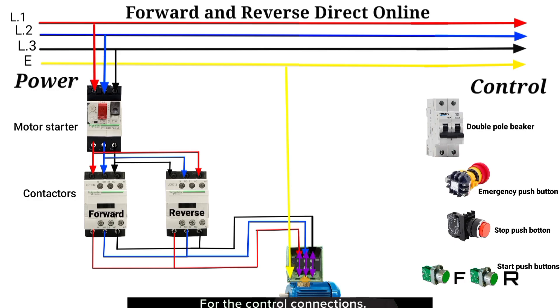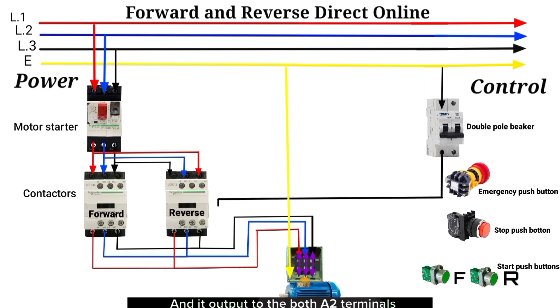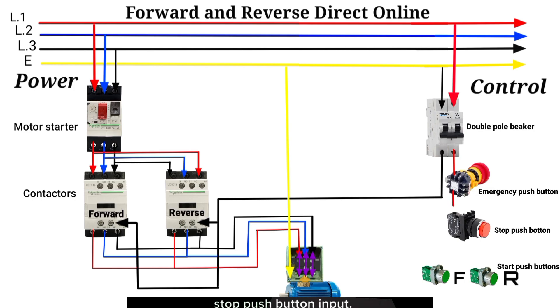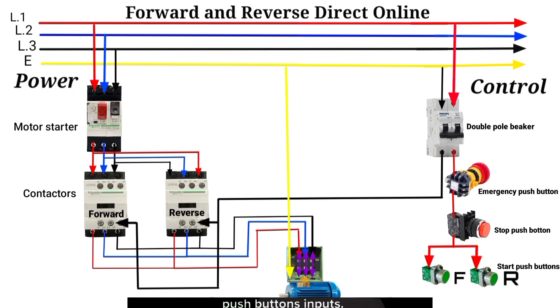For the control connections: neutral to the pole's breaker, and its output to both A2 terminals of the forward and reverse contactors. Live to the pole's breaker, and its output to the emergency push button input. Emergency push button output connects to the stop push button input. The stop push button output is then split to both the forward and reverse start push button inputs.